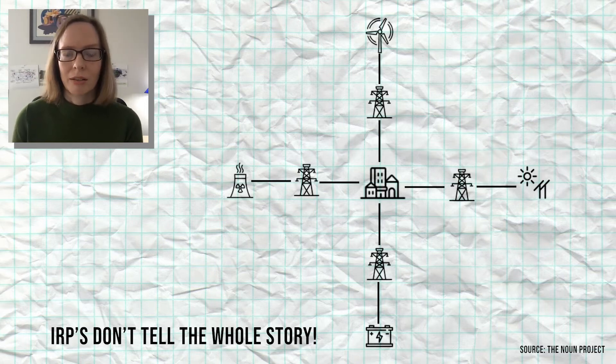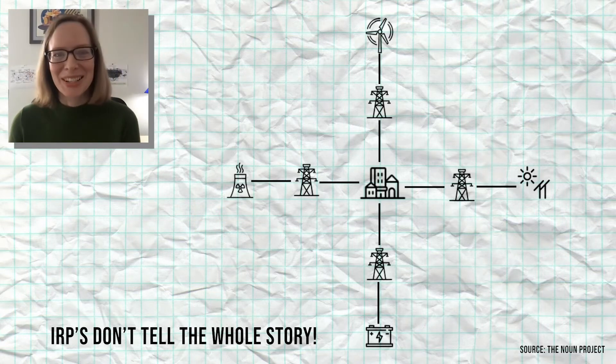Typically, a utility system doing an IRP for their service territory is not modeling the complicated transmission network as a web of interconnected lines. They're basically modeling their power plants, their resources, and their loads as if they're all in the same point — perfectly interconnected — so you don't have to worry about transmission constraints and losses. Maybe they'll model some purchases from outside the system or a remote resource with a transmission constraint on that import, but mostly they're over-simplifying the representation of the complicated grid.